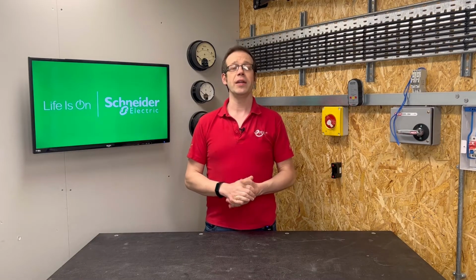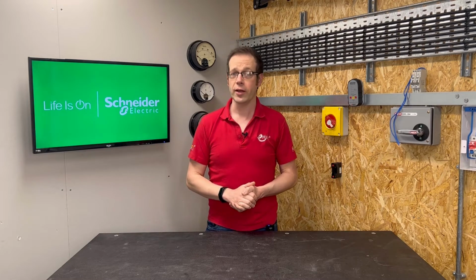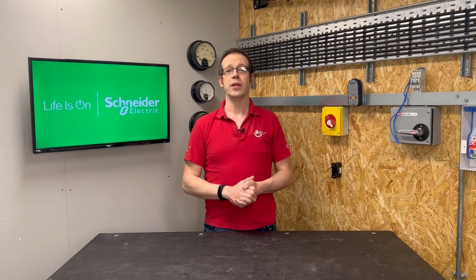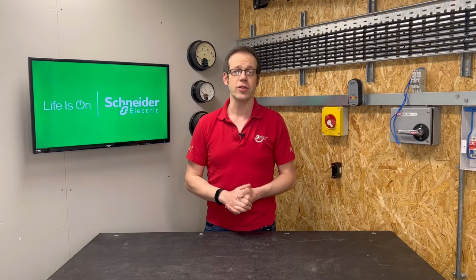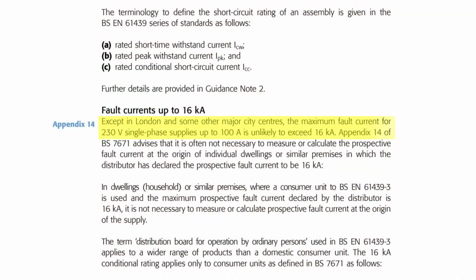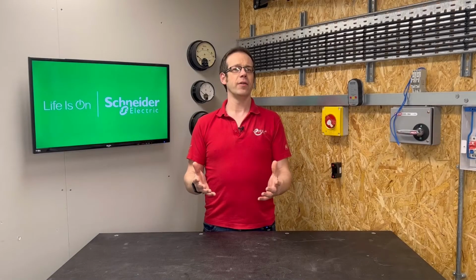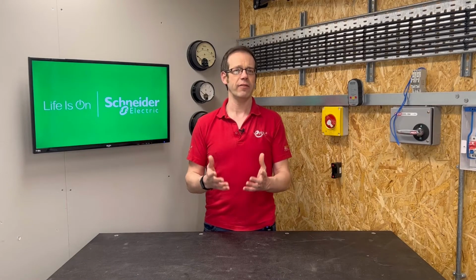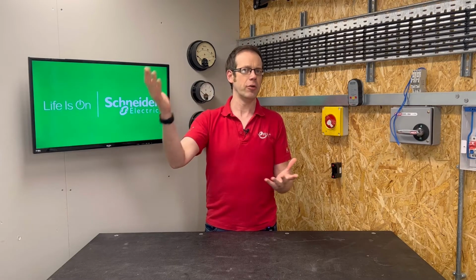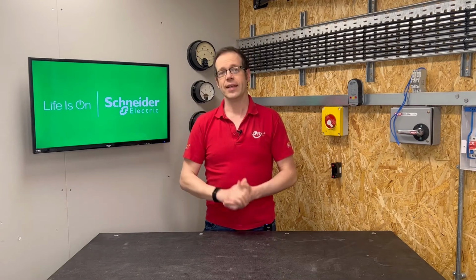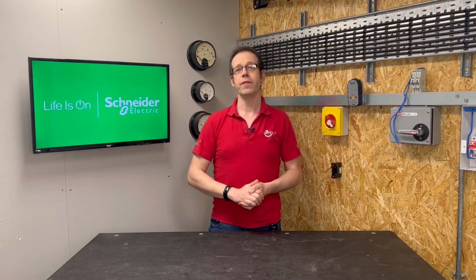The final option given is another method, which would be inquiry and asking your local distribution network operator for the value. Guidance Note 3 tells us that except in London and some other major city centres, the maximum fault current for a 230 volt single phase supply up to 100 amps is unlikely to exceed 16 kA. So if we're working with a declared fault current of 16 kA, shouldn't we have devices rated at 16 kA or above?